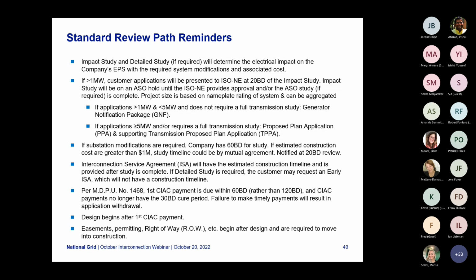Applications that are greater than 1 megawatt but less than 5 megawatts and do not require a full transmission study will require a GNF. While applications that are greater than or equal to 5 megawatts and/or do require a full transmission study will require PPA and supporting transmission proposed plan application. In cases where substation modifications are required, study timelines would allow for 60 business days. If estimated construction costs exceed 1 million, then the study timeline can be by mutual agreement, and in either case, this information is shared as part of the 20 business day review.